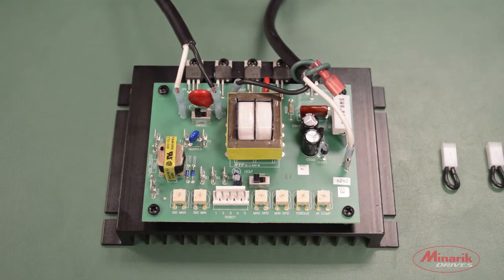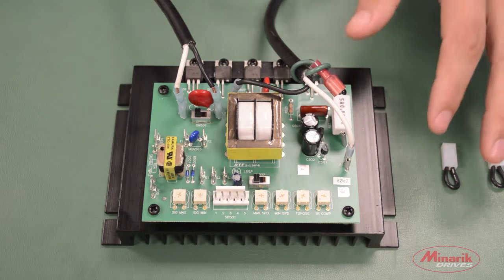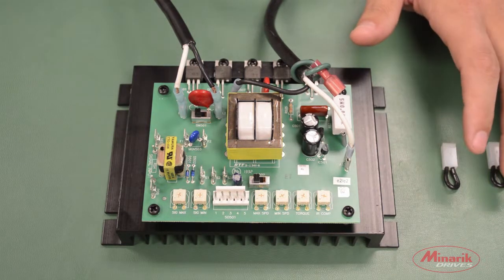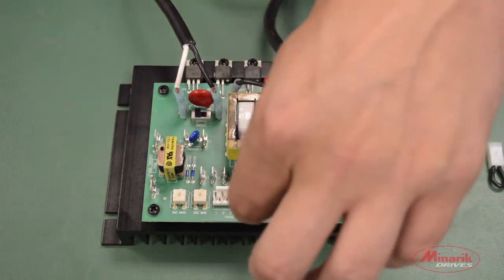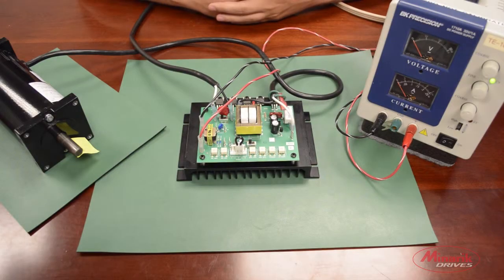The second mode is called signal follower mode. In this mode, the drive will follow a voltage input signal instead of a speed potentiometer. To achieve this mode, you have to short pins 3 and 4 on the mode select header block. Now we will demonstrate the drive in signal follower mode.